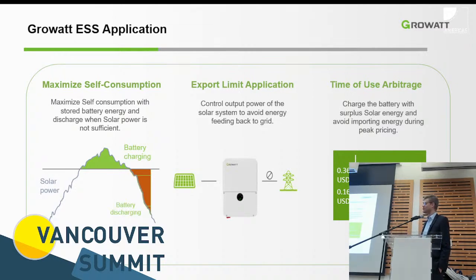That's the standard operation mode, for example, in all of Europe, and in Australia, because they have exactly that system where electricity is relatively high when you buy it, and you get whatever, 8.5 euro cents, when you feed it into the grid. So there's a huge incentive to look out for yourself first in your own interest, and then the excess power is given to the grid and to your neighbor. You can also do an export control with the same setup. An export control can be a zero feed-in, if it's all the way to zero, or it can be an export limitation to a certain power value. Since all of those systems with a battery system typically have a smart meter at your common point of coupling, you have the infrastructure already to implement all of those, let's say, smart control features for your system.